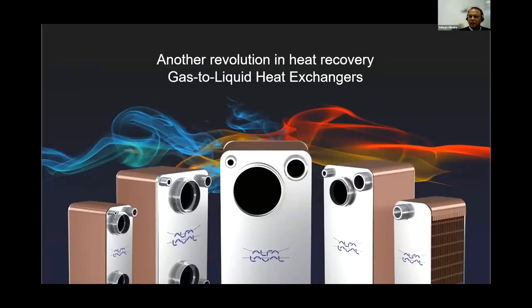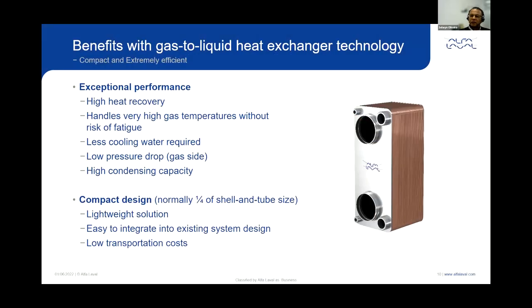Our new range of gas to liquid heat exchangers are a revolution in waste heat recovery. These heat exchangers offer several benefits. They have exceptional performance with advantages of high heat recovery, ability to handle very high gas temperatures without risk of fatigue, less cooling water required, low pressure drop on the gas side, and high condensing capacity. They're very compact with the resulting benefits of being lightweight, easy to install and integrate into the system together with lower freight cost. They take up a quarter of the space compared to traditional shell and tube heat exchangers.